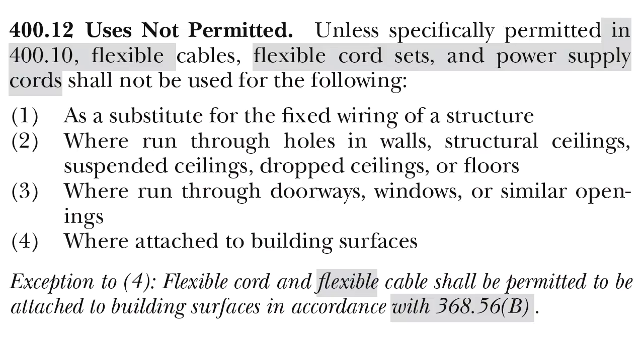Okay, 400.12, uses not permitted. Okay, let's take a look at this 400.12. Unless specifically permitted in 400, flexible cables, flexible cord sets, and power supply cords shall not be used in the following. What I find interesting in 400.12 in the 17 code is that there are no longer any rules that apply to flexible cords.